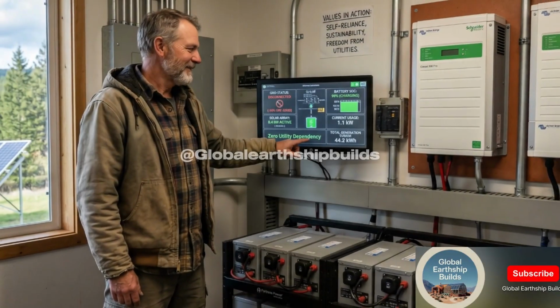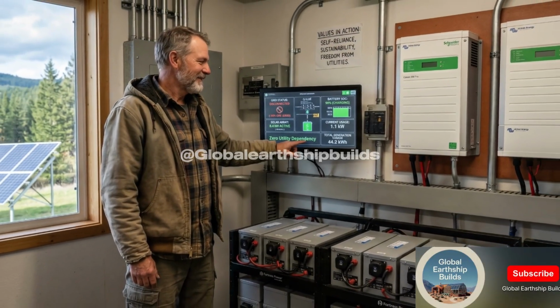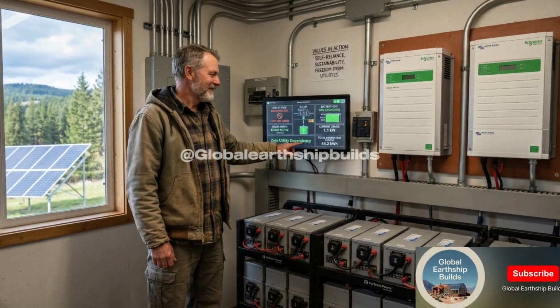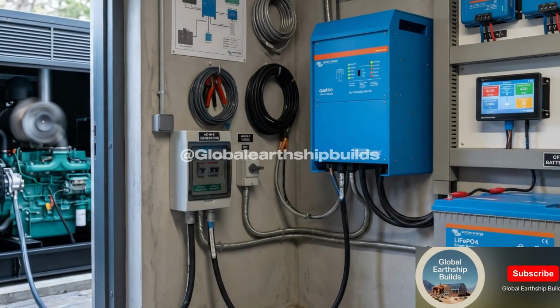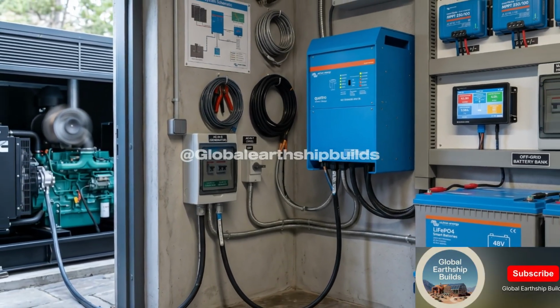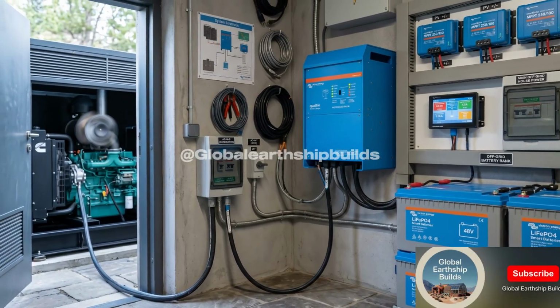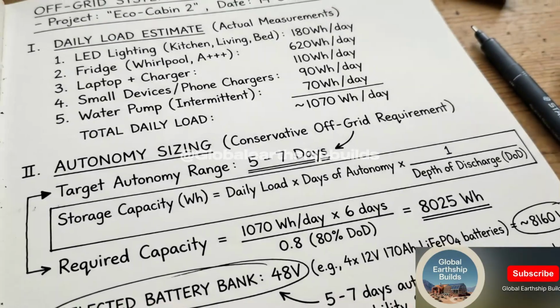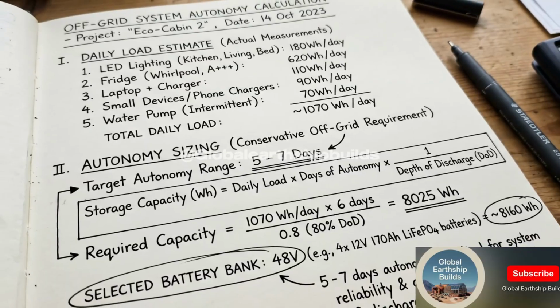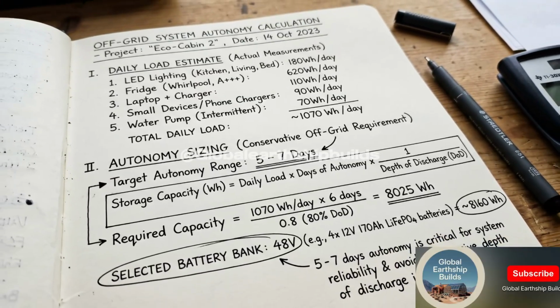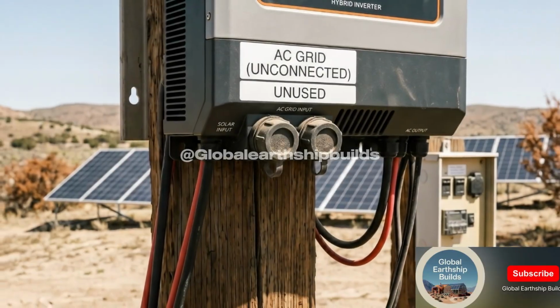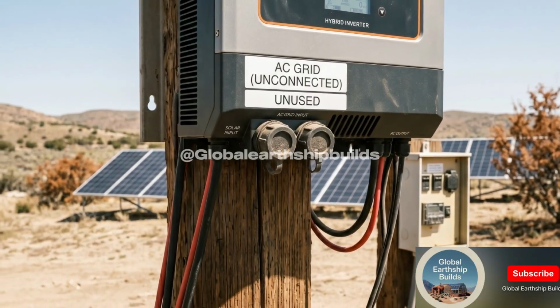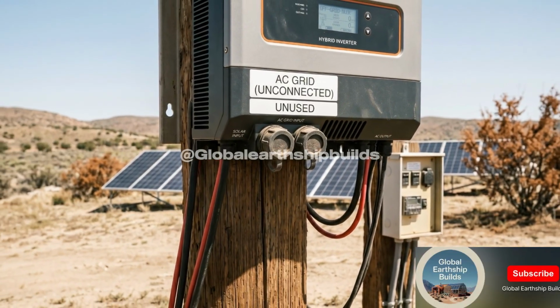The second scenario is maximum surge demand. If you are running a well pump, a large air compressor, a grain grinder, or other heavy motor start loads on your system, the transformer-based off-grid inverter handles those startup surges more cleanly and reliably than most hybrid alternatives. The Victron Multi+ and Quattro series are specifically engineered for these applications.